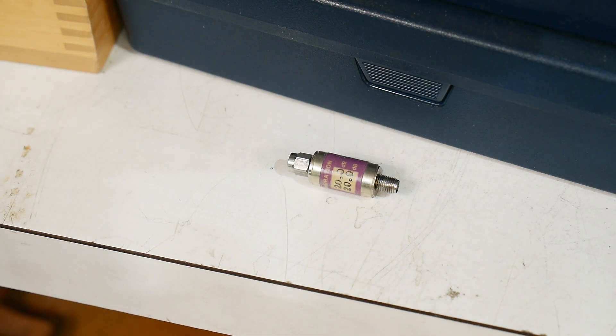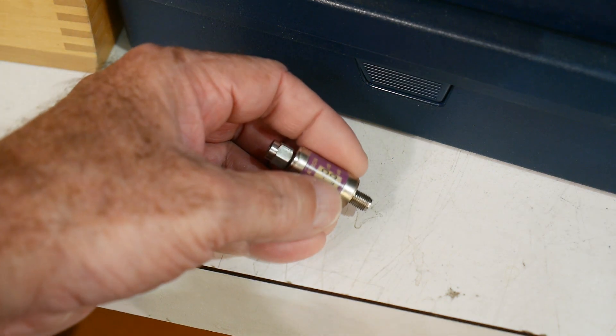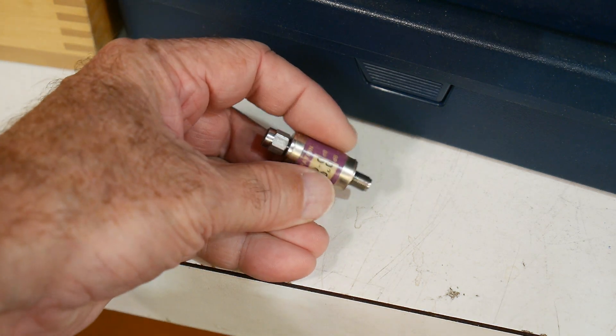So I wanted to point out that spectrum analyzers are not very accurate. They're good for relative measurements, but they're not really good for accurate measurements. So let's see if we can measure this thing the right way, all right?